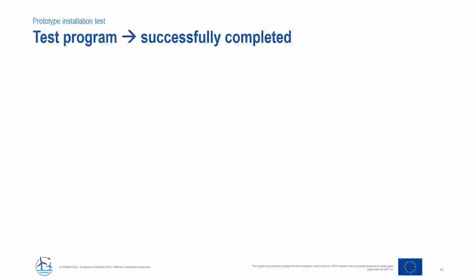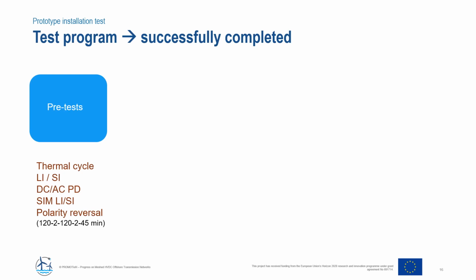prototype installation test itself. In this slide, I would like to present a test program that we have followed during this long-term test of HVDC GIS. Of course, the test program has been developed based on recommendations from CIGRE and also some wishes of end users. Before putting the HVDC GIS under long-term test, there are some steps that must be followed. In this case, it's a pre-test.